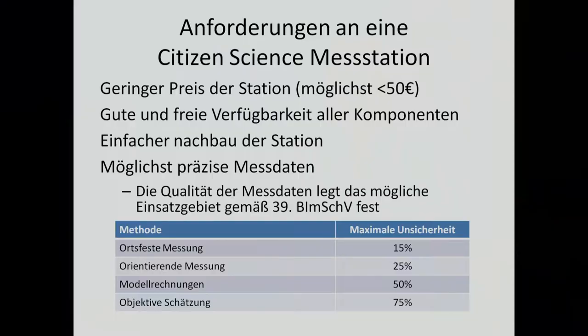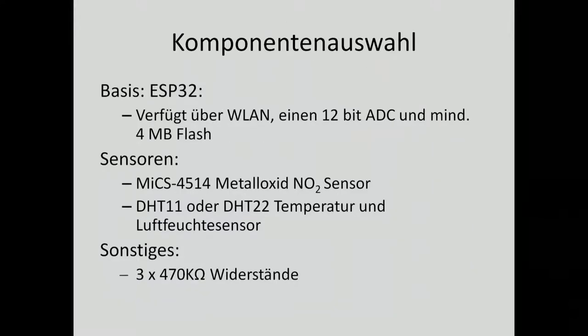Based on that, I formulated the requirements for a citizen science measurement station. It should be as cheap as possible, because nobody wants to spend tens of thousands of euros. The components should be widely available — usually they are only available for industrial players. It should be easy to build, and ideally as precise as possible, because you might want to present results to a government agency. Therefore we would like to stay within the framework of orientating measurements, with 25% uncertainty.